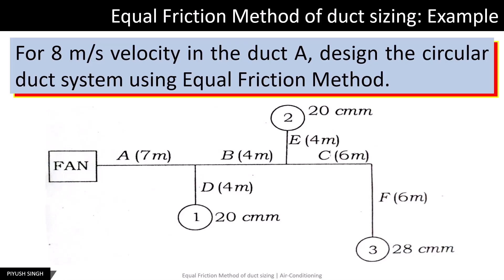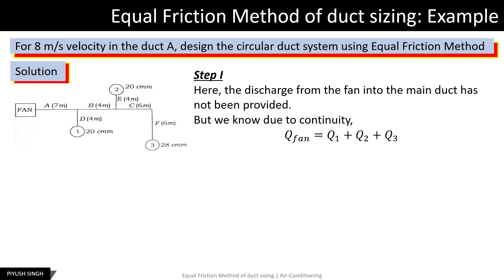Consider the duct system shown here. It is given that the velocity in the main duct A is 8 meters per second. We have to design a circular duct system using the equal friction method. In the first step, we calculate the discharge from the fan, which has not been provided. The discharge from the fan is equal to the air supply to the different zones. So Q_fan equals Q1 plus Q2 plus Q3, which comes out to be 68 CMM or 1.133 cubic meters per second.